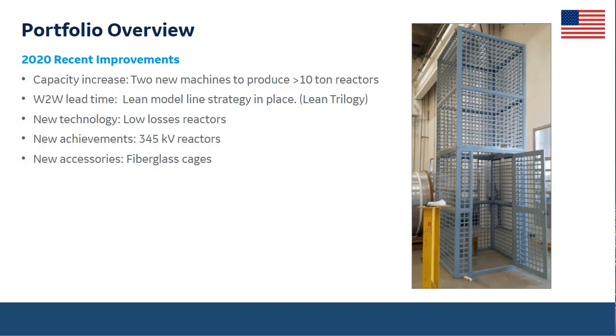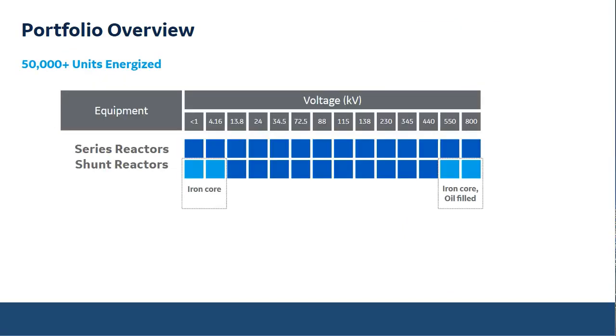We had designed a GE made fiberglass cage. So for example, in an open substation or inside a factory or a room where you have safety concerns, we can provide a fiberglass cage to avoid people touching and getting closer to the reactors. The advantage of fiberglass, I'll explain later when I talk about magnetic field, but that's a very good innovation when working with reactors. Just quick here on the portfolio.